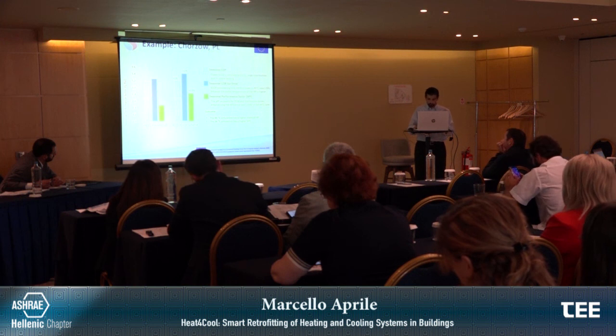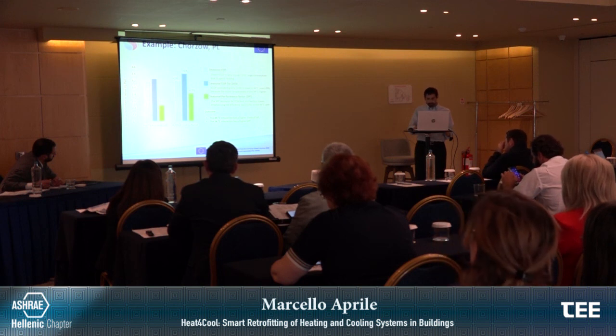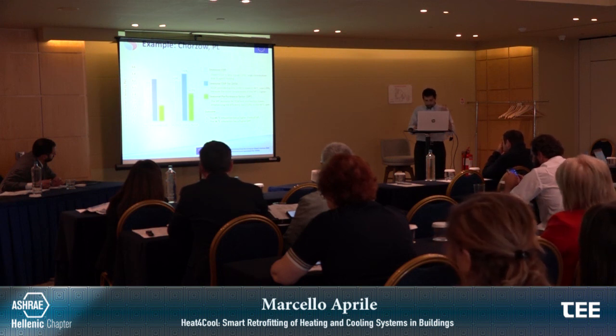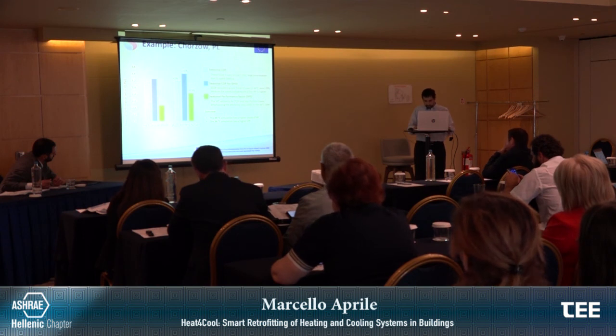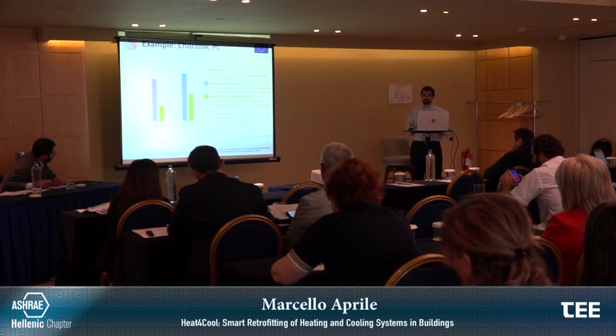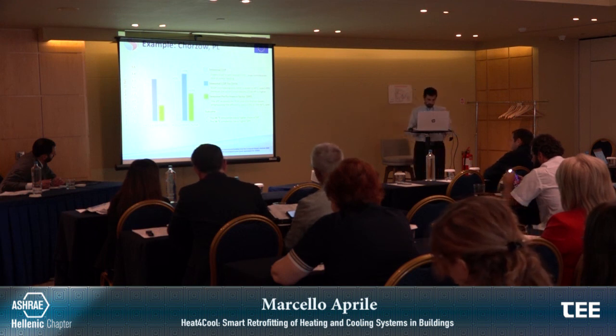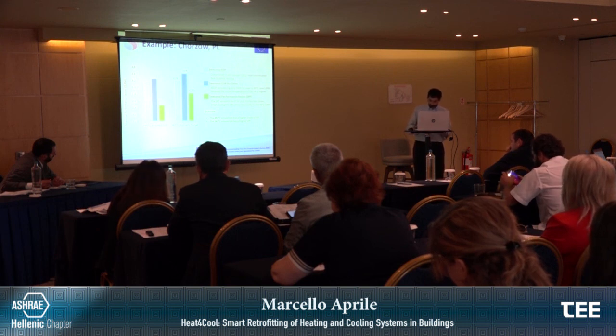So the choice is always a compromise between these two factors. What's important to stress is the evaluation of the most important performance indicator, which is of course the seasonal performance factor, not the COP of the heat pump. And here we see a consistent difference between the two phases.